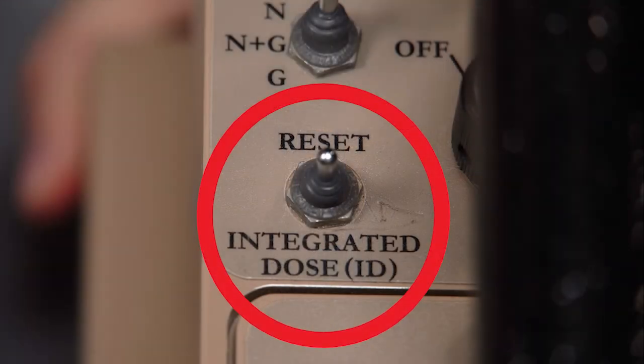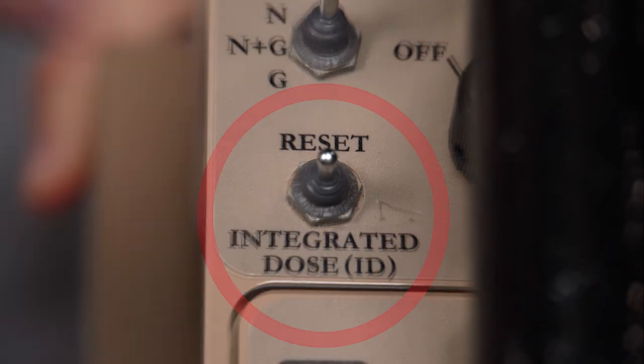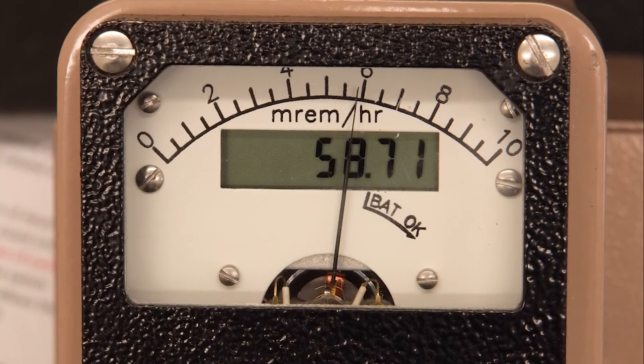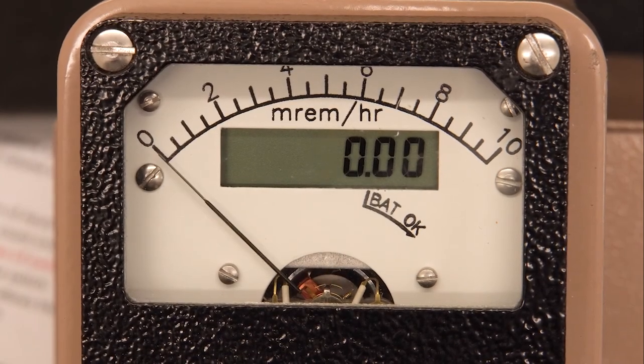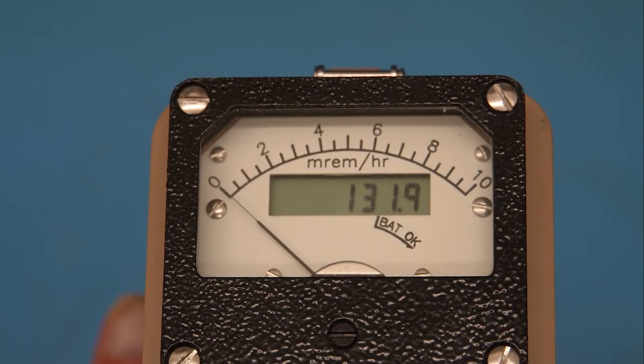A dual-position momentary toggle switch labeled Reset and Integrated Dose. When the Reset position is selected, this switch provides a rapid means of driving the analog rate meter to zero. When the Integrated Dose position is selected, it reads out the integrated dose.